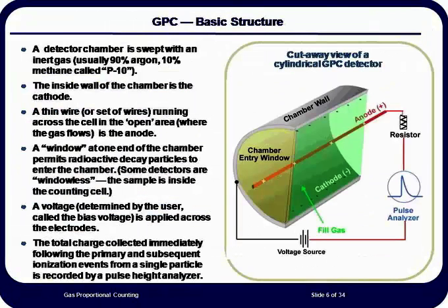The diagram on the right shows a cutaway view of a basic gas proportional counter that has a thin window. This means that the sample is located outside the active detector area, in this case the flowing argon gas. The walls of the detector cell are the cathode and the central detection wire is the anode. If no voltage were applied across these two portions of the cell, and ionizing radiation caused an ion pair to form, the ion pairs would recombine because there is no driving force for them to separate.